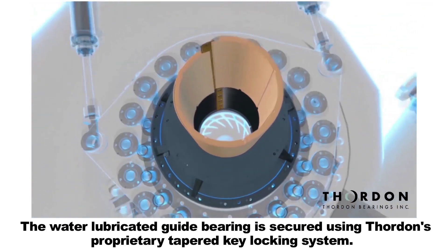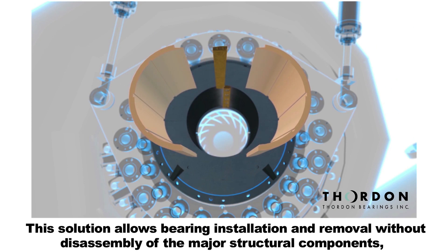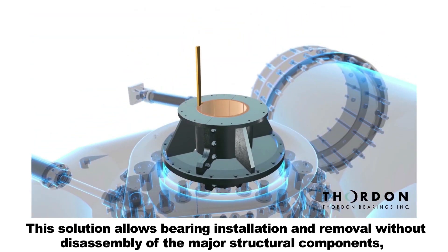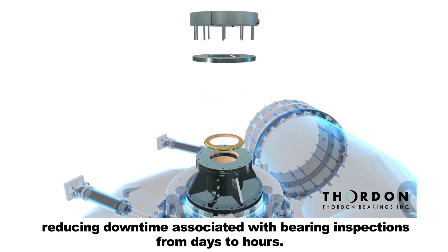The water lubricated guide bearing is secured using Thordon's proprietary tapered key locking system. This solution allows bearing installation and removal without disassembly of the major structural components, reducing downtime associated with bearing inspections from days to hours.